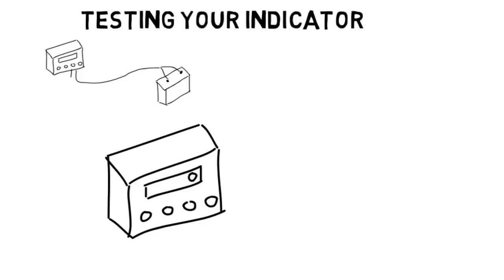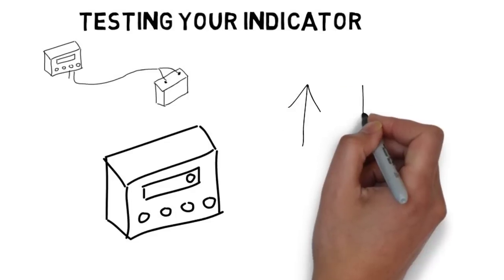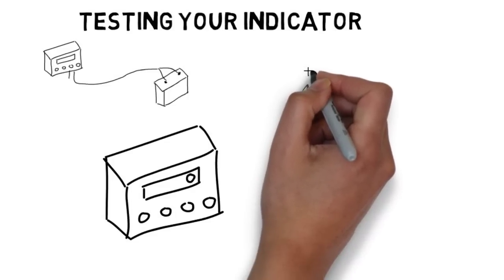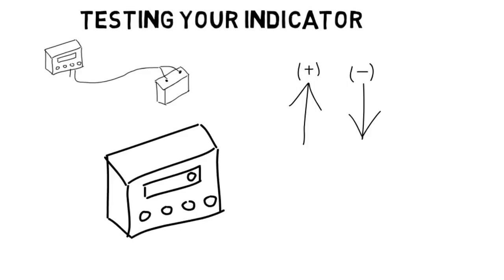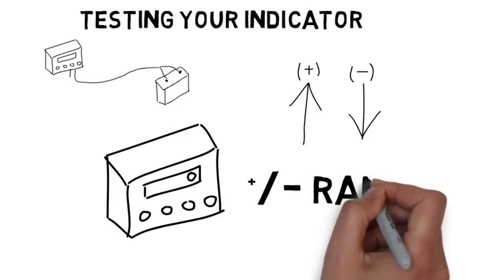Sometimes it takes two or three times to zero your indicator, simply due to the fact that your indicator is adjusting its filtering for the change in input from the load cells. This is normal. It should zero after two or three times and remain stable at zero, plus or minus five pounds. If it drifts positive or negative, or displays plus range or minus range, you may need to send your indicator in to us for repair.